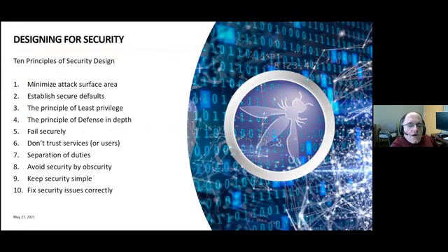When we talk about designing for security, you want to consider minimizing the attack surfaces on your device and establishing secure defaults. That means you're not asking someone to turn a feature on to make it secure. By default, out of the box, the device is secure. It doesn't have "password" as a password or some default weak setting, so that if a user doesn't do what they should, the device is still going to be secure. You want to make sure that if a user connects this to a network that's not secure, or almost to the internet, it is still going to be secure.